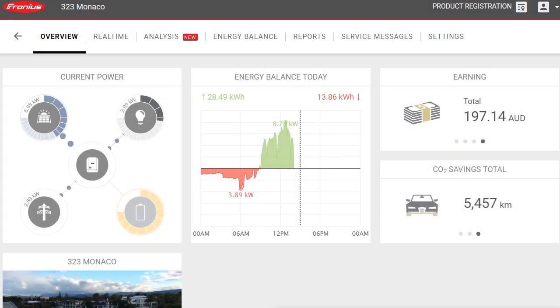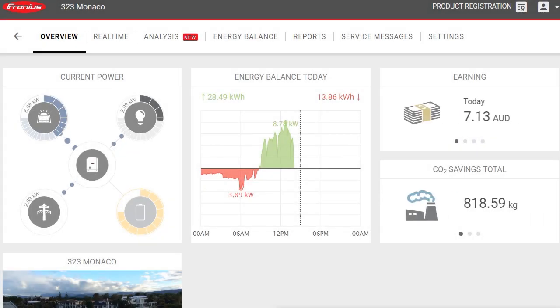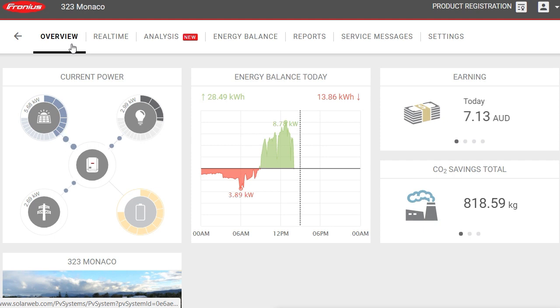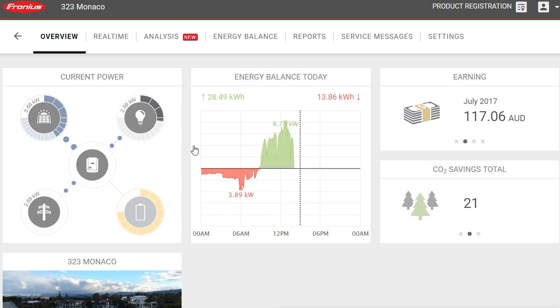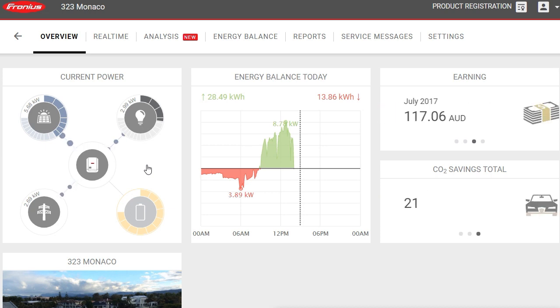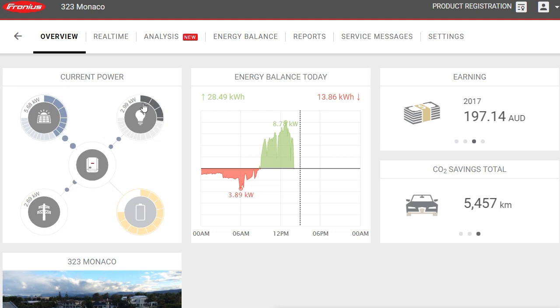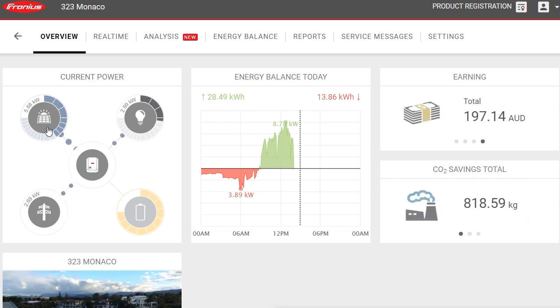Here we're looking at the Fronius Solar Web monitoring platform. At the top we have a number of tabs; we're currently on the overview tab. The main thing you see here is the current power of the system. This system has a Fronius smart meter, which can show us the consumption of the property and the power going to or from the grid. The solar panels are right now producing 5.68 kilowatts of power, fed into the solar inverter.